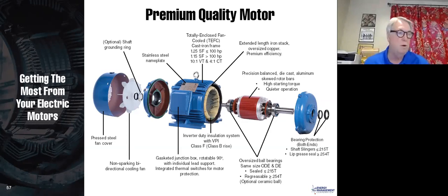Now, if bearings are the number one reason for failure, then wouldn't you want to figure out how you can make your bearings last longer? Well, the first thing you can do is use oversized bearings. If the bearings are oversized, they will tend to last longer. Second thing to do is use bearing protection, such as shaft slingers or lip grease seals. That keeps particulate out of the bearing. You want to keep that bearing clean. And if you have dust and grime and particulate getting into the bearing, that is going to shorten the life of the bearing. Next, you can use a cast iron frame motor, which we've already talked about, in order to make sure those bearings are in alignment. And if you will do that, you will significantly increase the lifetime of your motor. And of course, keep the motor running cool.